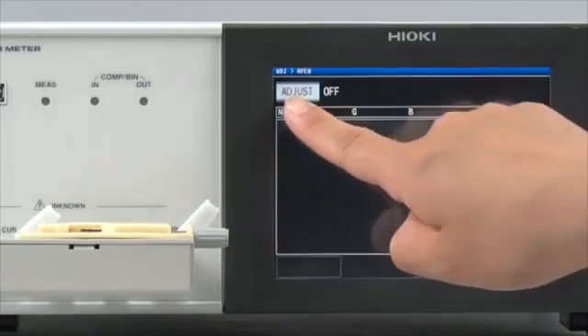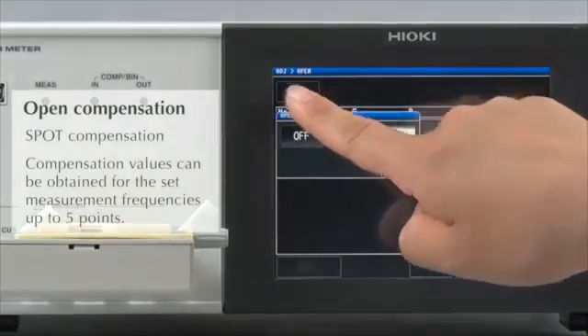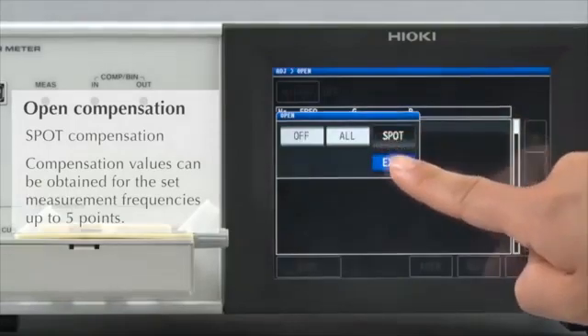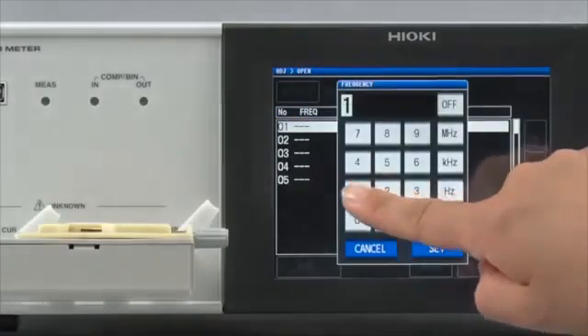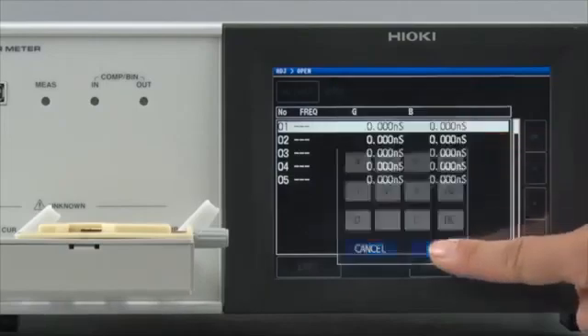First, conduct open compensation. Since we are only measuring at 1 MHz this time, spot compensation is sufficient. Set at 1 MHz.